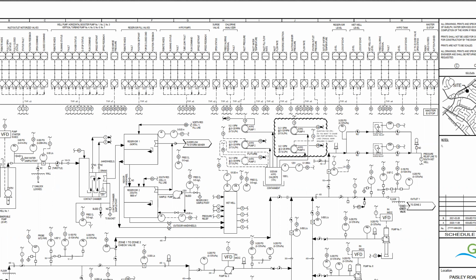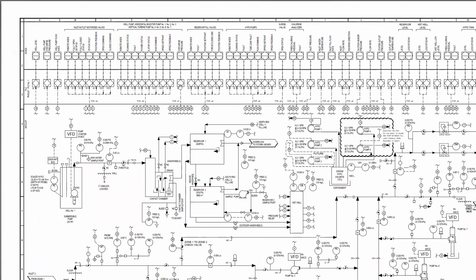So if you were going to start quoting and building a control panel based on these drawings, you could go through and see you've got well pumps, horizontal booster pumps, and vertical turbine pumps, and they all have the same IO points. And we got 8 of them. So 5 times 8 plus 1 times 8. So 16 AI, 8 AO, 8 DO, and 40 DI just for these pumps. Based on 16-point input cards, we need 3 digital input cards only for these pumps. If you want to spread them all out, you're probably going to want to do 4, so you can do 2 per, so you can always have some available, or maybe you want to do 1 each plus.